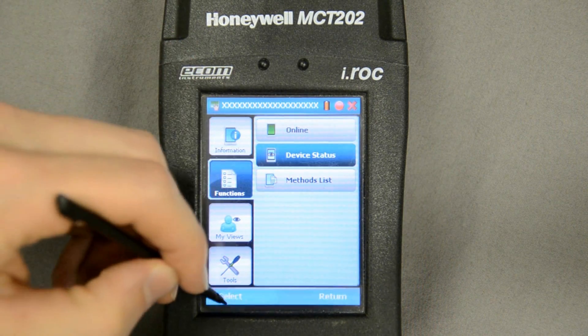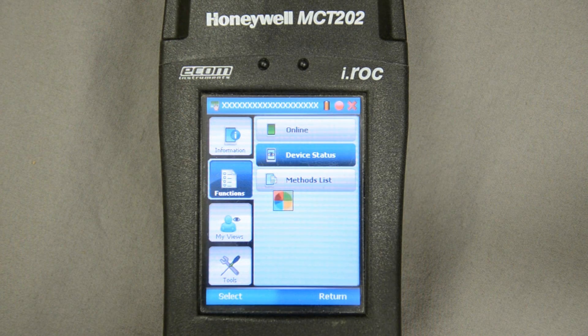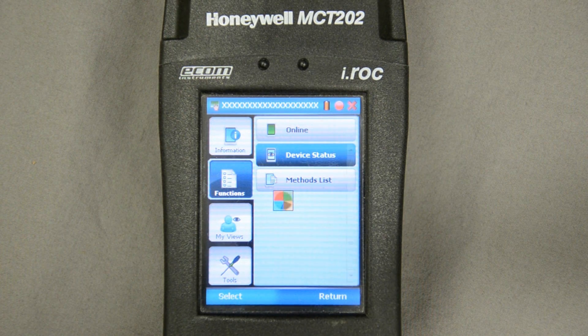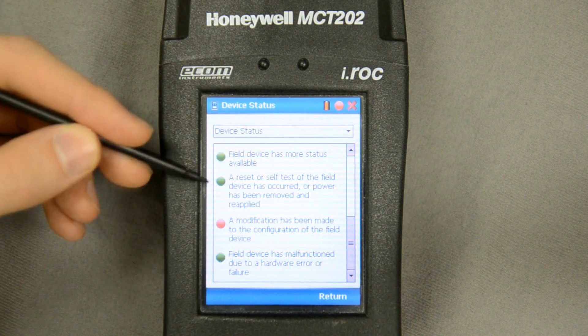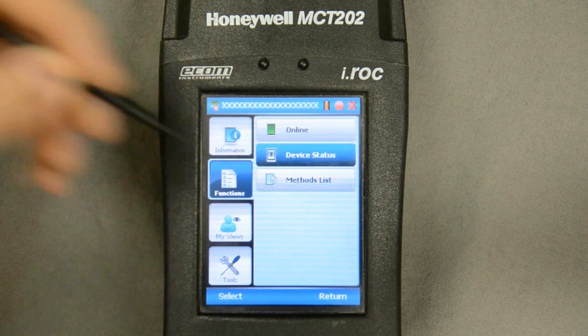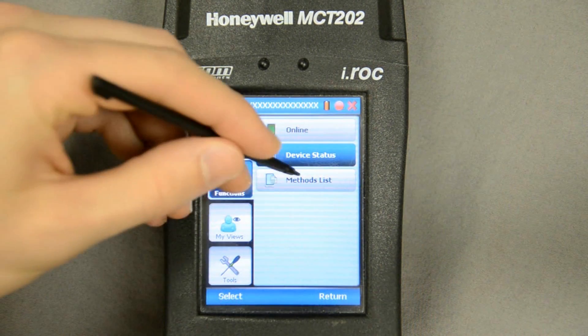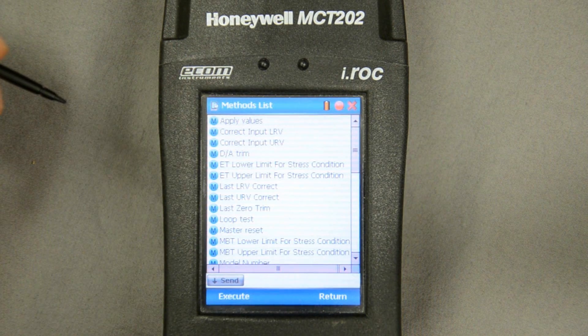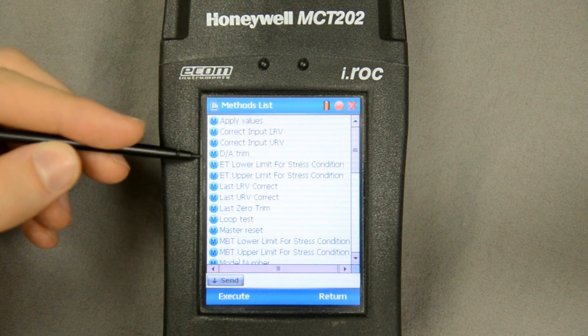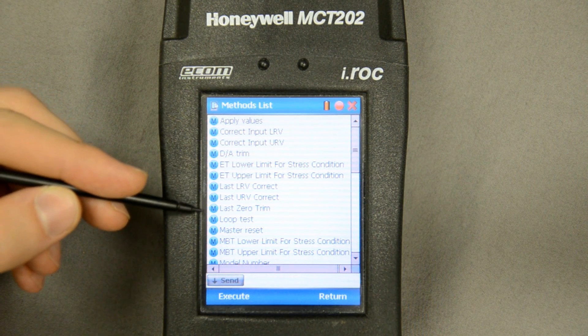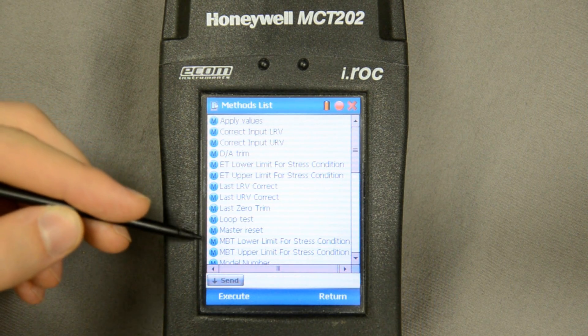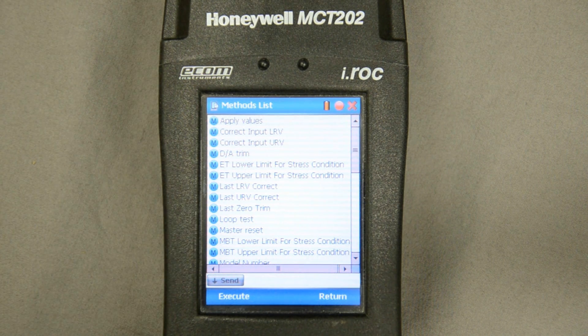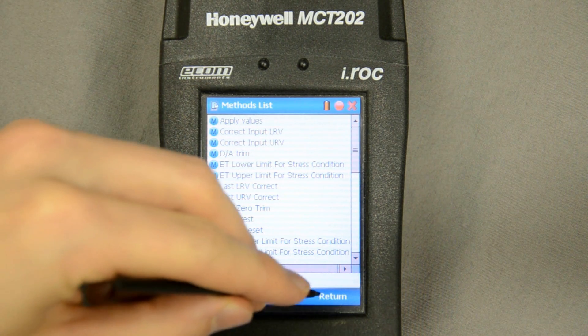Down here I can save the history of what I do to the transmitter. The function screen is the main screen you're going to be working off of. On the device status, selecting that gives me some recent history of the transmitter — any configuration changes will be stored here. I can go to the methods list, which gives me a whole list of executables I can perform on the transmitter, for instance a loop test, a sensor trim, or zeroing the input.